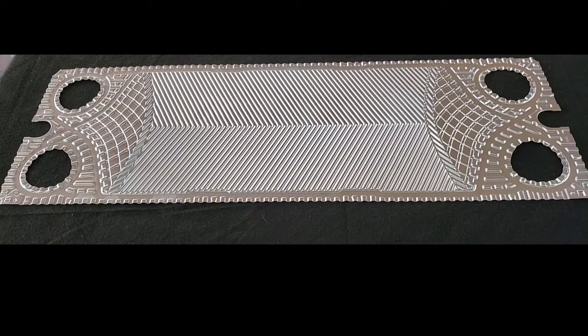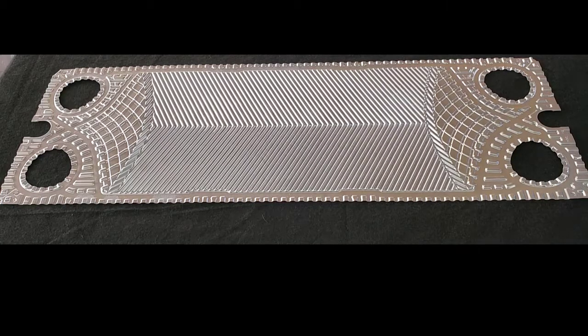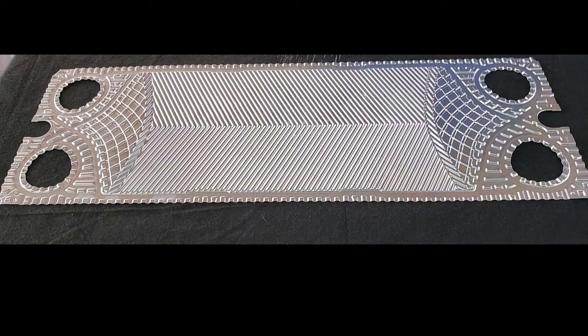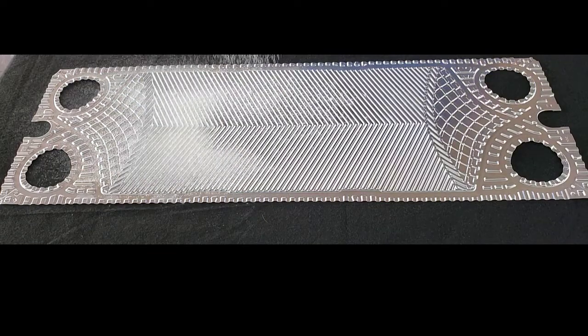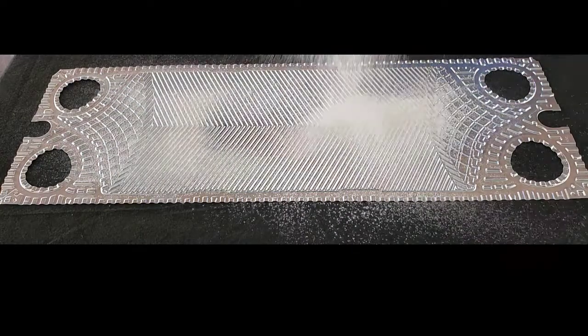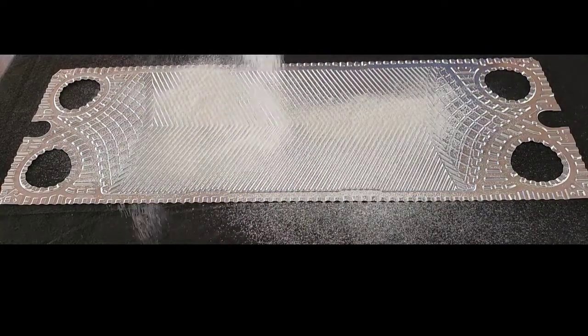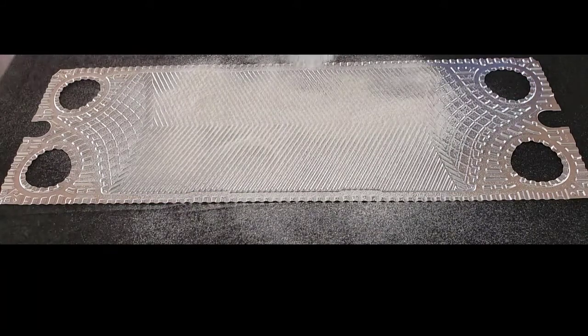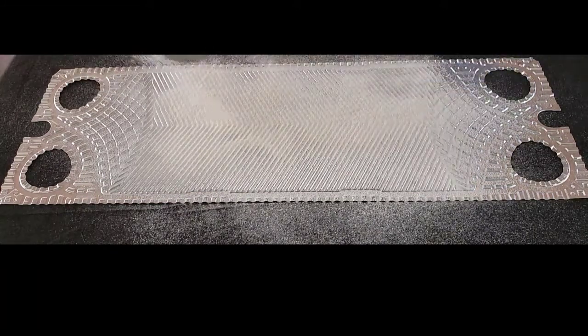This is a plate in a plate and frame heat exchanger, and over time, particularly if you run the heat exchanger at a reduced flow or your liquid is very dirty, you experience buildup on the surface of your plate called fouling. Fouling is negative: it makes heat transfer from the two sides of the plate harder, reducing heat transfer efficiency, and it clogs the channels, increasing the pressure drop.